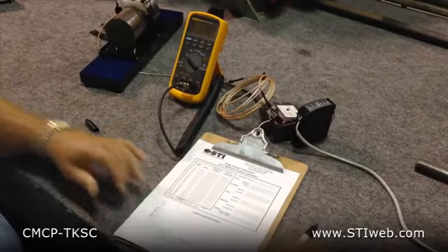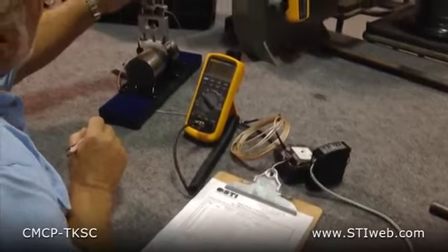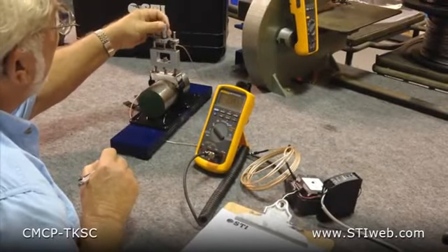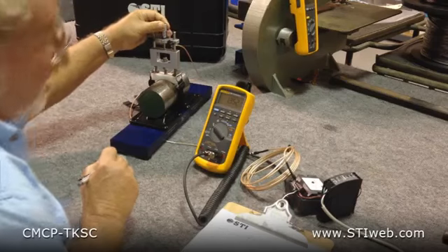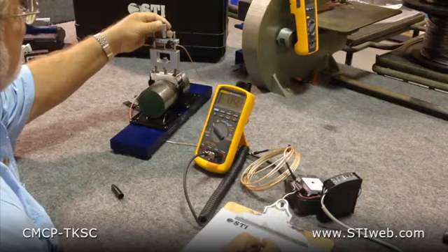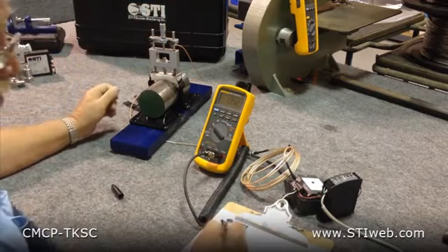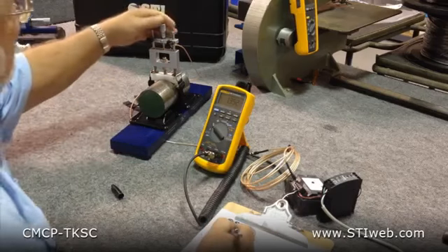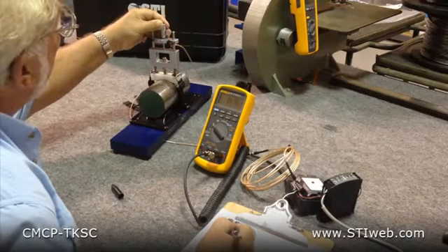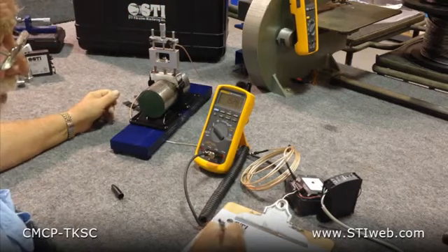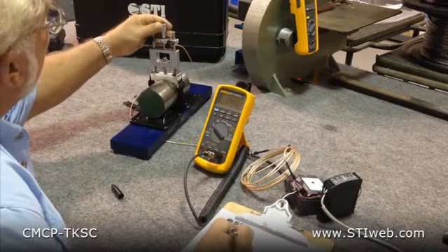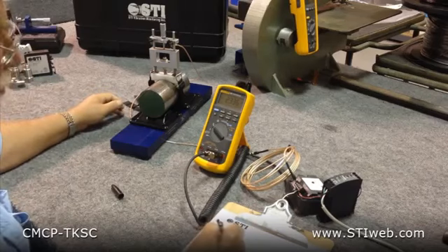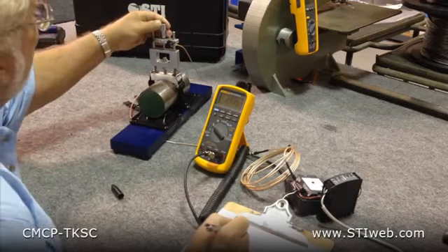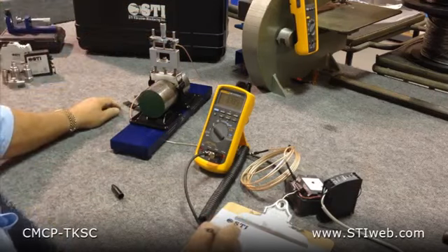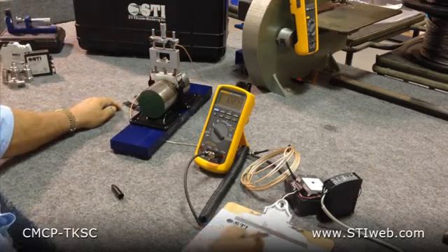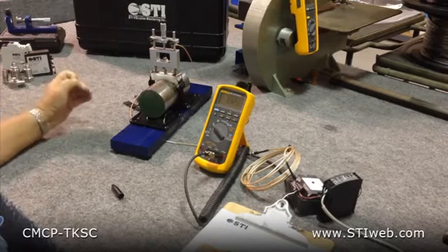Okay, back to doing a standard calibration curve. What we do is we go back to the 0 point, which is when the proximity probe is touching the metal. Now we start moving out in 5 mil increments. So at 5 mils, we write down the voltage, 1.352. That's a negative, by the way. We go to 10 mils, and you'll notice that it's fairly easy to line up. We got minus 1.529. At 15, we got minus 2.336. You see the probe is actually coming in range now. And at 20 mils, we got minus 3.321. And we keep doing this for 5 mil increments until we roll off the other end, and you'll actually see when the probe quits responding.